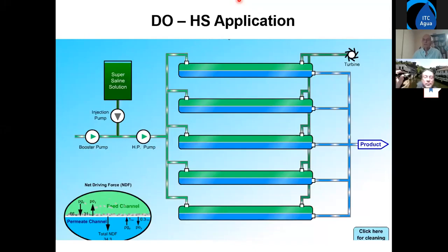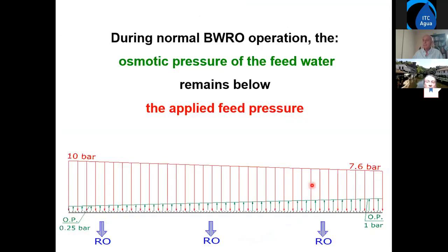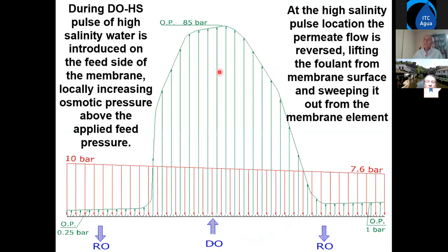In this cleaning, before the high pressure pump, we have a super saline solution, a high concentration solution, close to 18% of sodium chloride, which we open the tank and let some plug flow of high saline solution flow through the system in normal operation.